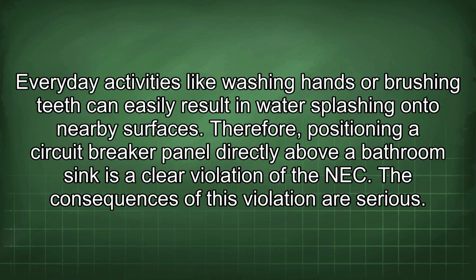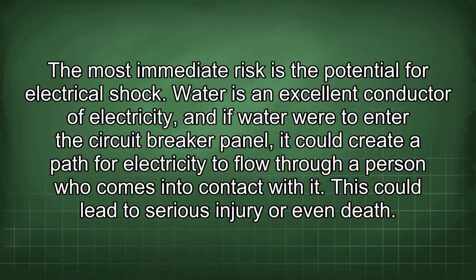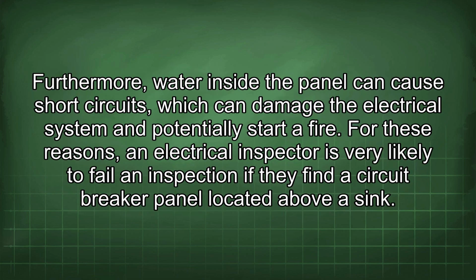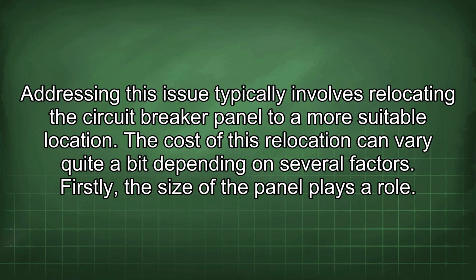The consequences of this violation are serious. The most immediate risk is the potential for electrical shock. Water is an excellent conductor of electricity, and if water were to enter the circuit breaker panel, it could create a path for electricity to flow through a person who comes into contact with it. This could lead to serious injury or even death. Furthermore, water inside the panel can cause short circuits, which can damage the electrical system and potentially start a fire. For these reasons, an electrical inspector is very likely to fail an inspection if they find a circuit breaker panel located above a sink. Addressing this issue typically involves relocating the circuit breaker panel to a more suitable location.